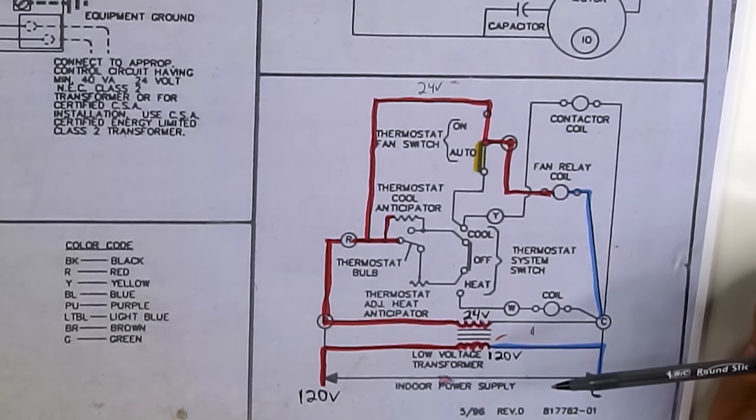The connection diagram is the same thing, just set up differently. Let's take a look at it. Right here it says connect to appropriate control circuit having 24 volts. That will be the thin solid line coming from inside the house from the control board or thermostat — basically from the transformer sending out 24 volts. We have the hot leg and the common leg, usually a two-wire thermostat wire going outside to the contactor. In this case it's two purple wires, shown with two wire nuts, meaning the thermostat wire from the house will connect via wire nuts to wires that lead to the contactor coil.